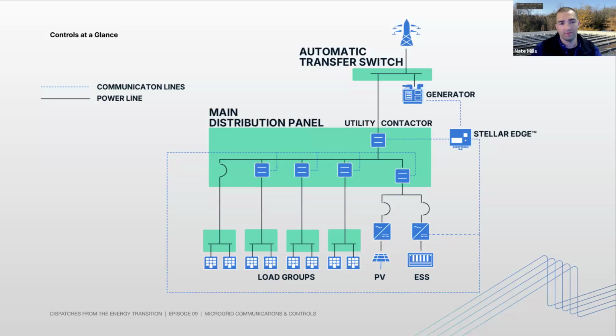For example, if you have a load shedding contactor and you lose communication with it, or you lose relay power to it, and it's a normally open contactor like most are, then if it's a critical or essential load, we want a way to bypass that contactor. The key is to anticipate that need as much as you can and build it in. What we don't have is completely redundant communication paths between all the things that might need it, because that gets out of hand in both cost and complexity pretty fast.